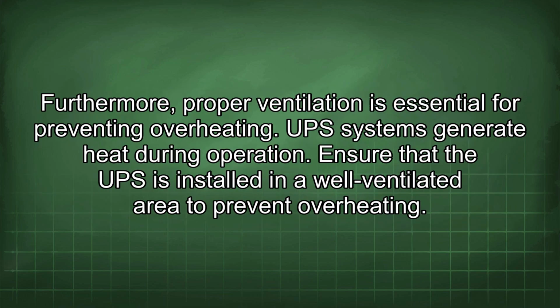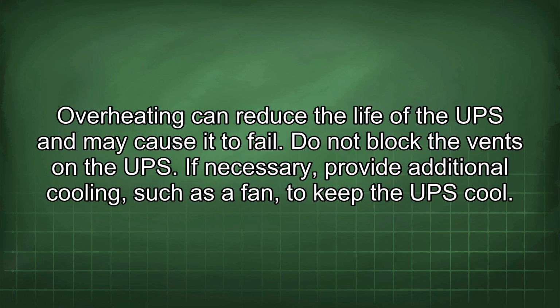Furthermore, proper ventilation is essential for preventing overheating. UPS systems generate heat during operation. Ensure that the UPS is installed in a well-ventilated area to prevent overheating. Overheating can reduce the life of the UPS and may cause it to fail. Do not block the vents on the UPS. If necessary, provide additional cooling, such as a fan, to keep the UPS cool.